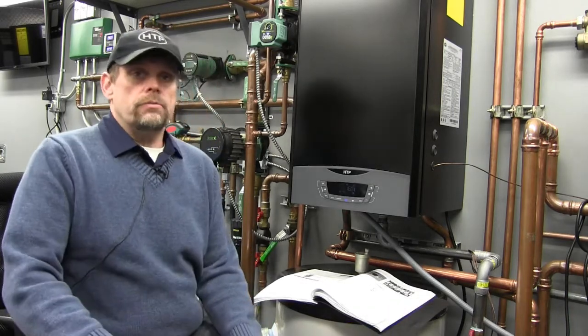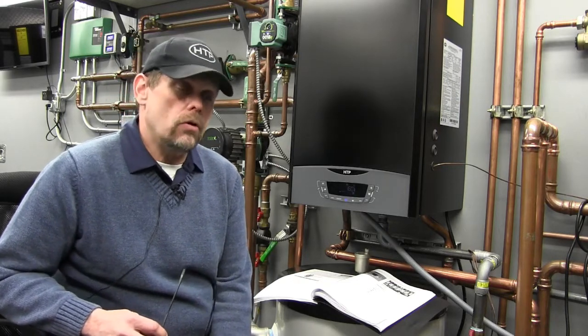The control on the Elite Ultra is the same control throughout the entire boiler line, be it operating a combi boiler or a heat-only application. It's the same control. When the boiler is purchased, that boiler will be pre-programmed and defaulted for the appropriate boiler, whether it's a combi or a heat-only. In the future, should that control need to be replaced, there are parameters in the control menu that you would go ahead and tell that control exactly what it is attached to now.